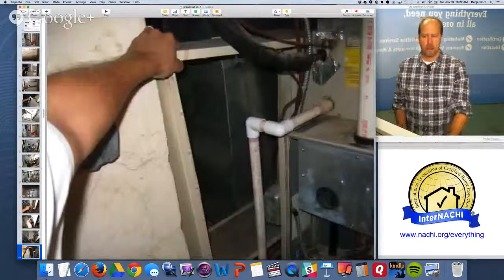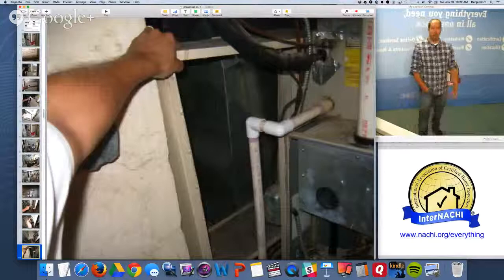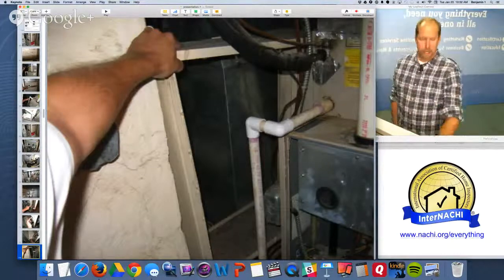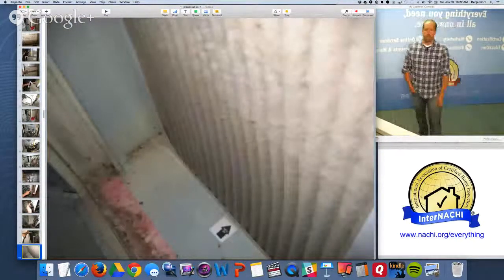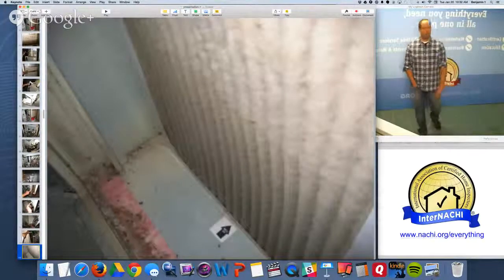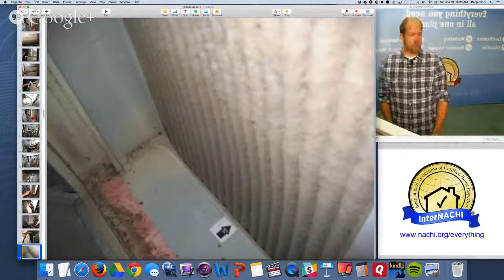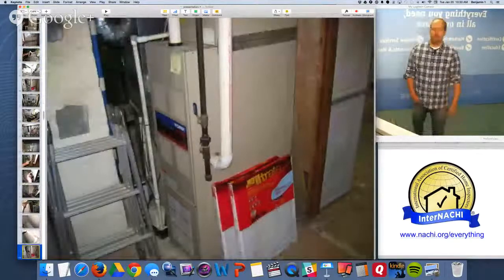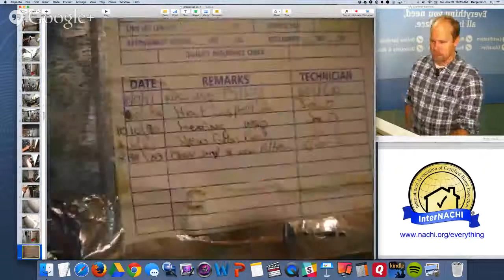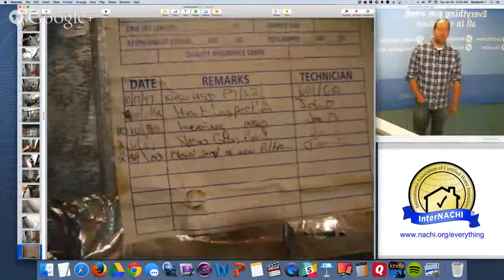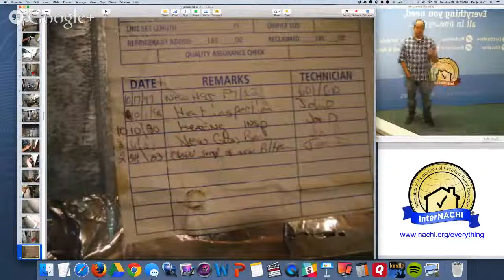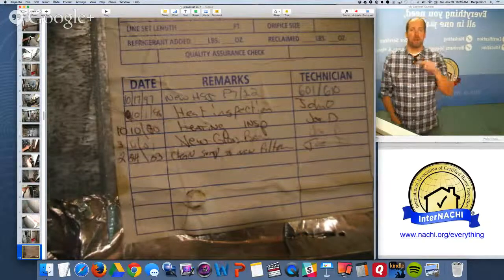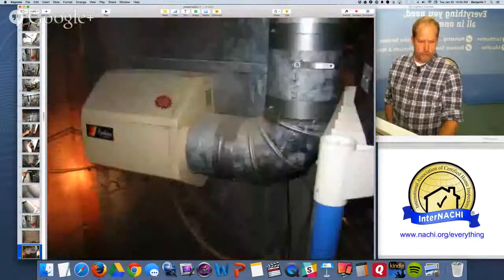They pulled out the high-efficiency filter and it's missing — they threw it away because it got dirty. These filters are kind of expensive but really good. Instead they put in a half-inch low-efficiency disposable filter that should be replaced every 30 days. This one is actually clogged and bowing in. They actually have new filters right there next to the heating system but didn't install them. I also take pictures of all the service labels — manufacturing labels on the systems and the service record — I want to tell my client the last time this was serviced, the date, what was done, and by whom.